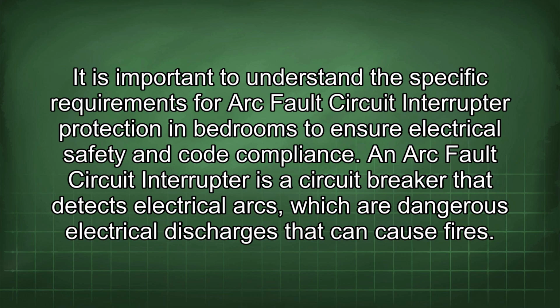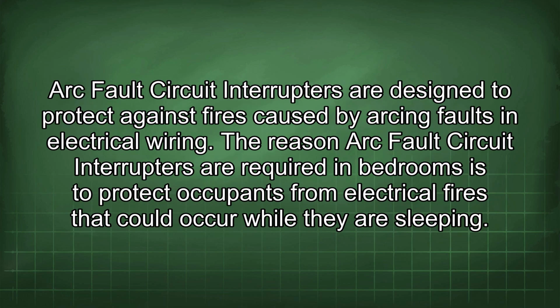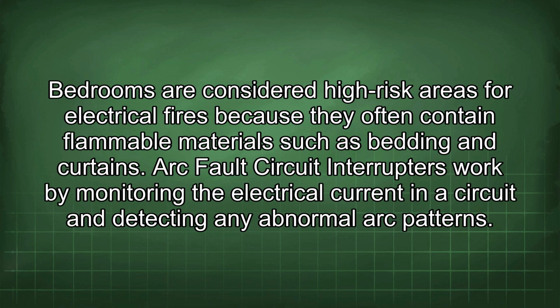An arc fault circuit interrupter is a circuit breaker that detects electrical arcs, which are dangerous electrical discharges that can cause fires. Arc fault circuit interrupters are designed to protect against fires caused by arcing faults in electrical wiring. The reason they are required in bedrooms is to protect occupants from electrical fires that could occur while they are sleeping. Bedrooms are considered high-risk areas for electrical fires because they often contain flammable materials such as bedding and curtains.